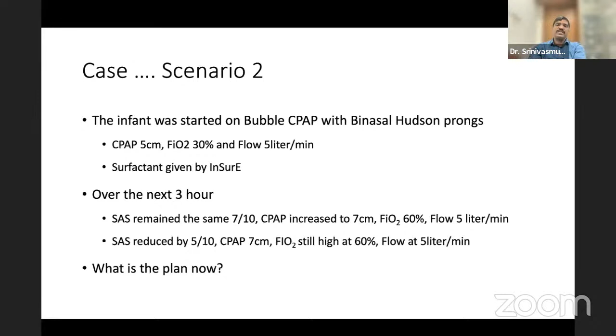And also look for humidification. On the humidifier, you should see a temperature of 37. There should not be any water in the inspiratory limb, and there should be some condensation in the expiratory limb, to say that actually you're giving a temperature of 37 and a relative humidity of 100% to the nose. That means you're giving warm and humidified gases to the nose. And that is what you have to do when you're giving CPAP for all babies. So 50% of CPAP is delivering the gases at 37 with a relative humidity of 100%. Another 50% is delivering the correct pressure to the lungs. So ensure that your CPAP is delivered appropriately before you take another action of correcting the hemodynamics, or going up more on the pressures, or giving a second dose of surfactant, or NIV or ventilation.